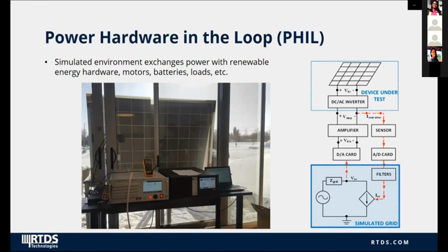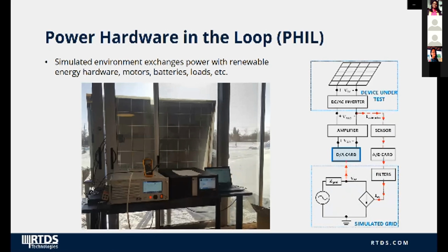The digital real-time simulator outputs the voltage which is to be applied to the terminals of the PV microinverter. The simulator is connected to the D2A converter, which scales down the signal to electronic levels within plus or minus 10 volts peak. These voltage levels are well below the operating voltage range of the microinverter. Therefore, an amplifier is required in the power hardware in the loop simulation to amplify the voltage to reasonable levels.